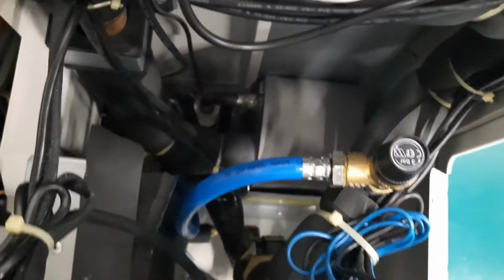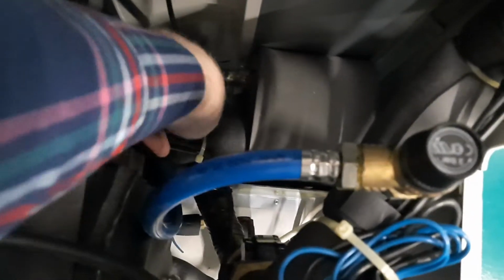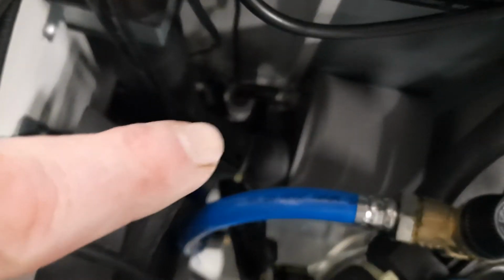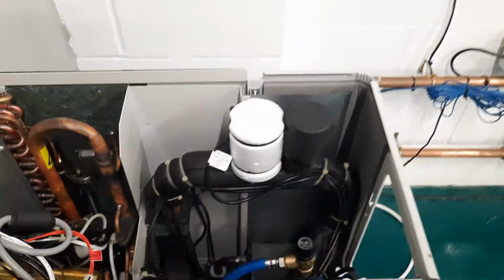So looking over the top, I've taken the lid off, which is about 6 screws. This is the heat exchanger. Down here is the pipework, refrigerant pipework, and notice that there is a sensor here coming down the back with a black tag on it. That sensor is just underneath the insulation. You can see right there. So check it's in place and the fault code will go away.